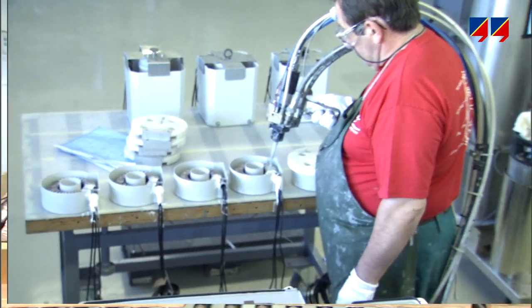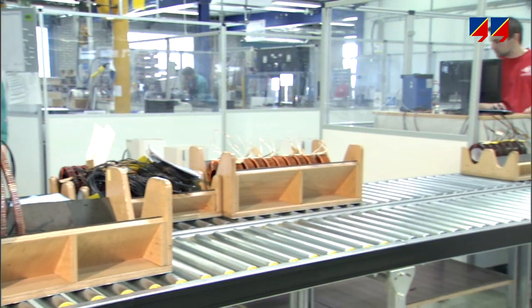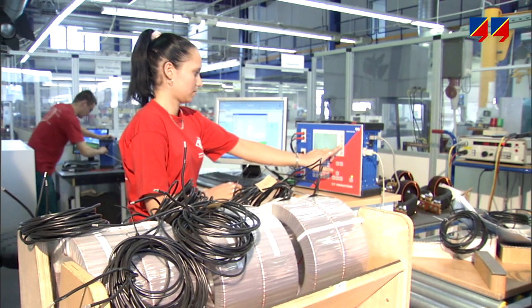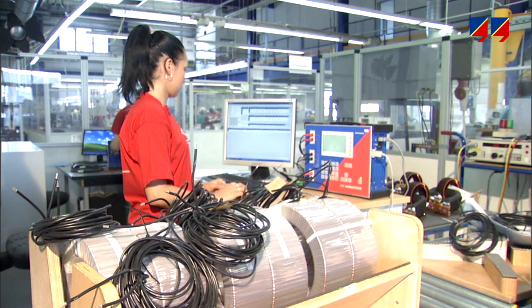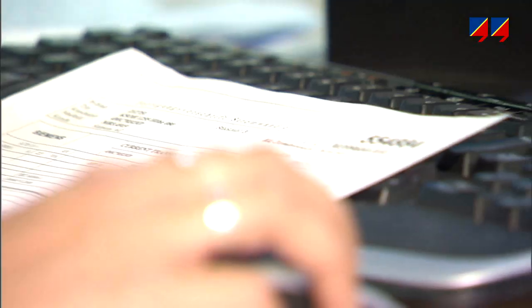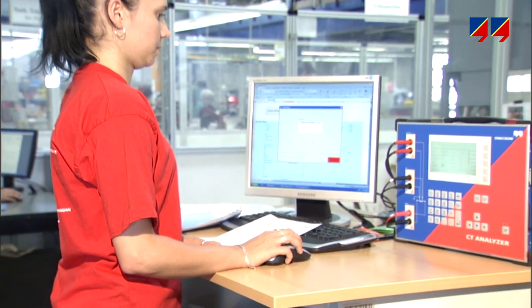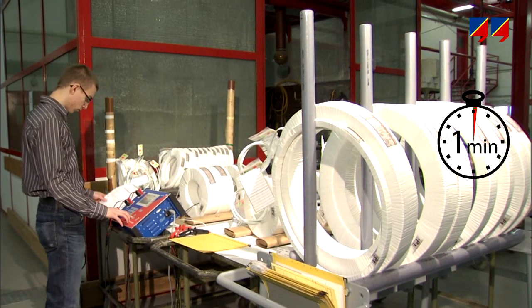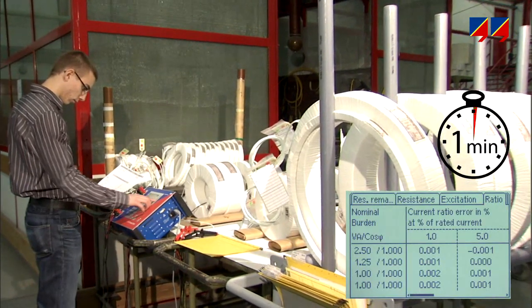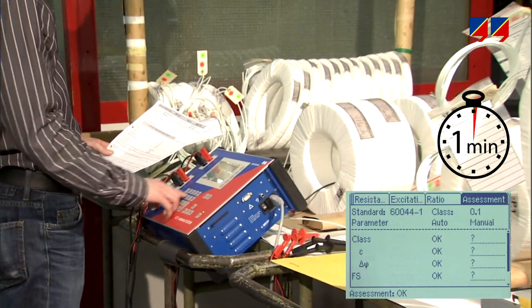Prior to the next stage of the CT's manufacturing process, which may be embedding it into resin, a further intermediate test is usually performed, as corrections can still be made. CT analyzer can perform such intermediate tests, checking whether the CT will fulfill its specifications or if further adaptations are required. CT analyzer performs these tests with little wiring effort and in a short time, with an accuracy equivalent to the bridge measurement method usually used for final testing. With a test duration of typically one minute, CT analyzer measures the winding resistance, the excitation curve, the turns ratio, and the accuracy values for the current and burden values defined in the relevant standards.